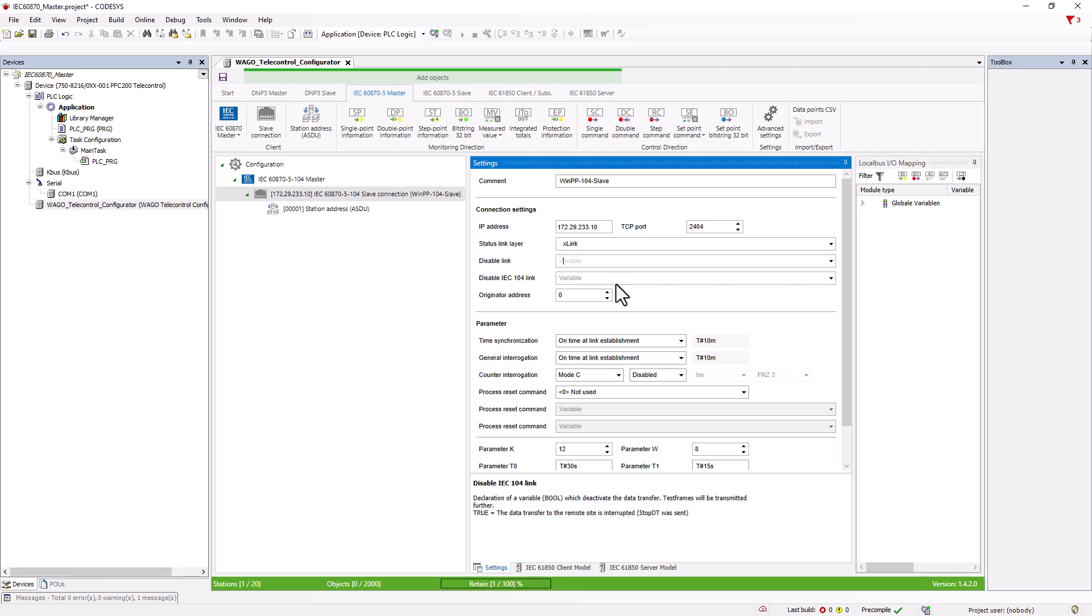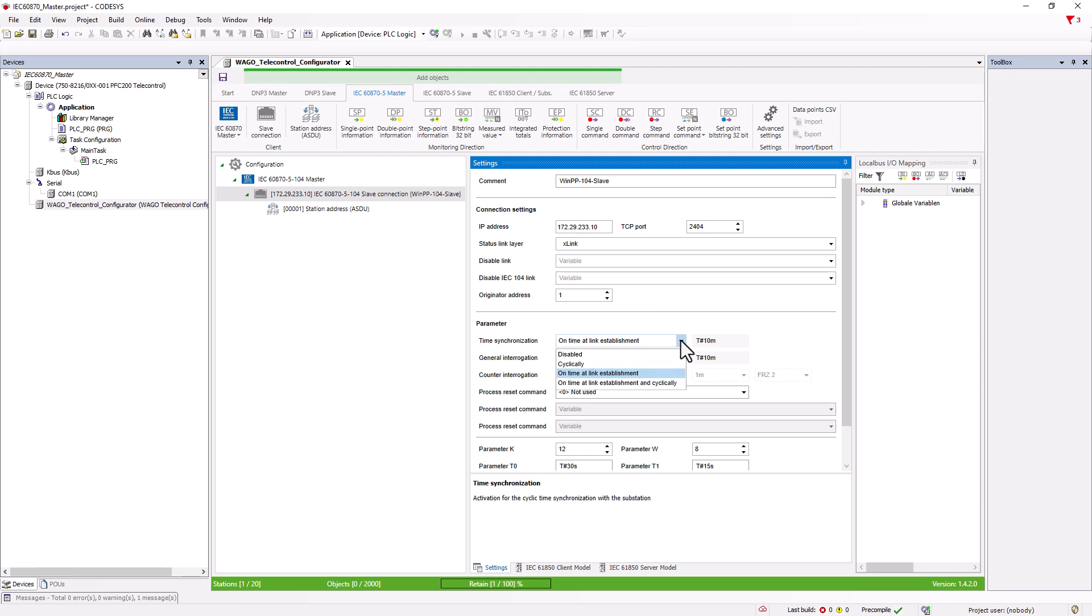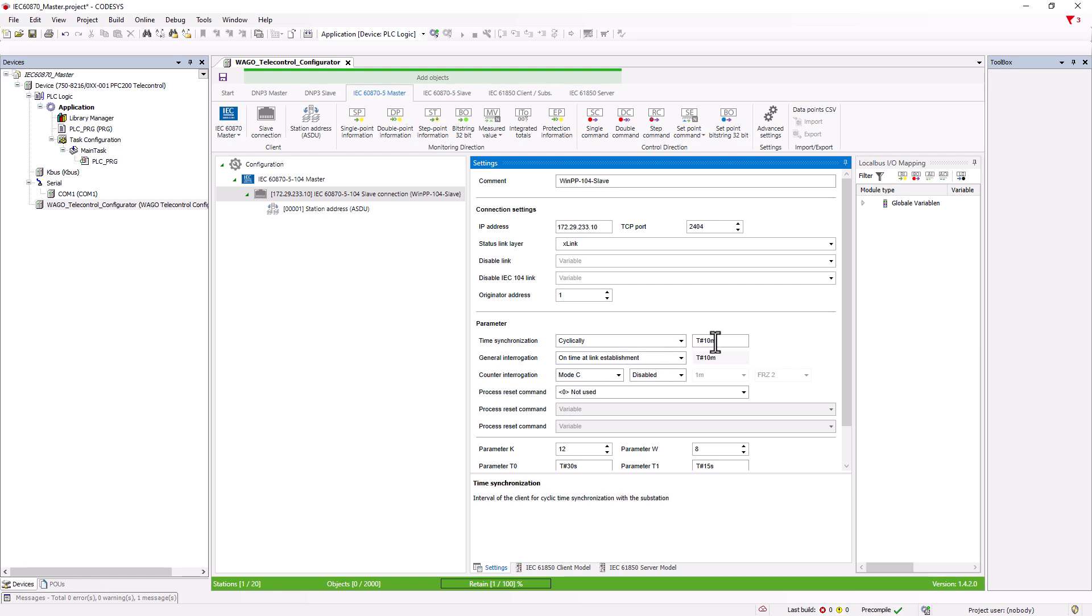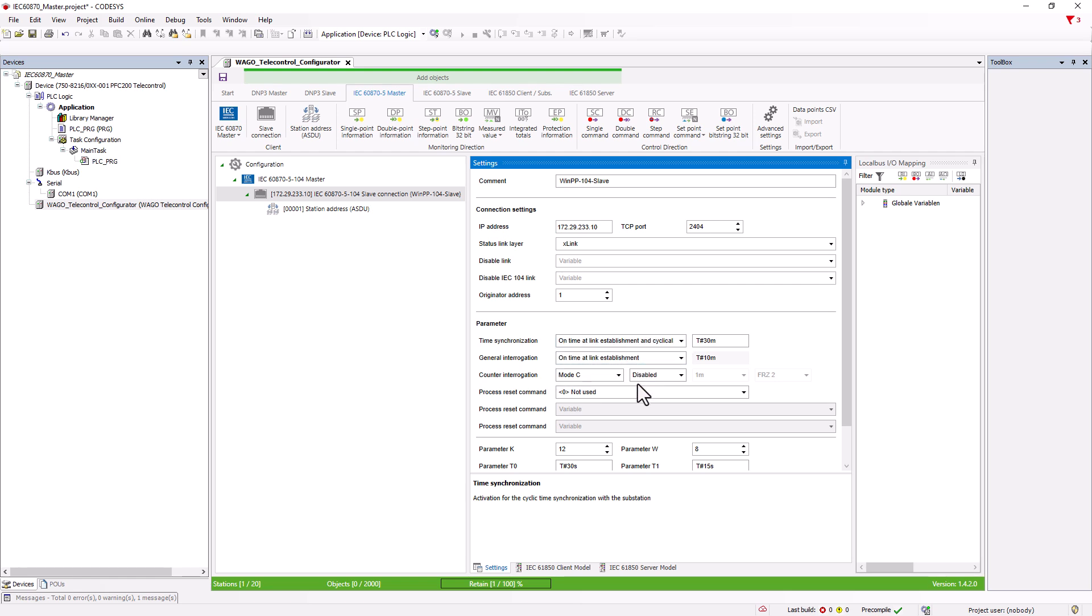The origin address of the master can be specified here. For time synchronization, we specify when the time synchronization object 103 should be sent. Disabled in the event that the slave synchronizes the time via an NTP server and does not require the object 103. Cyclically, for example, every 30 minutes, once when the link is established or altogether when link is established, and cyclically. The general interrogation trigger can also be set.